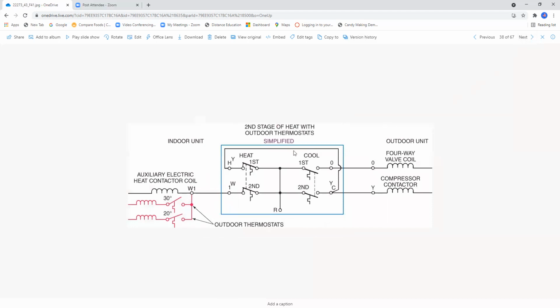Okay, here we have a situation where we have the second stage of heat with an outdoor stat. So basically what we're doing is we reach the balance point of this heating portion of the heat pump. In other words, the heat pump can't keep up with the cold air infiltration of the structure, so we may have to energize the auxiliary heat contactor.